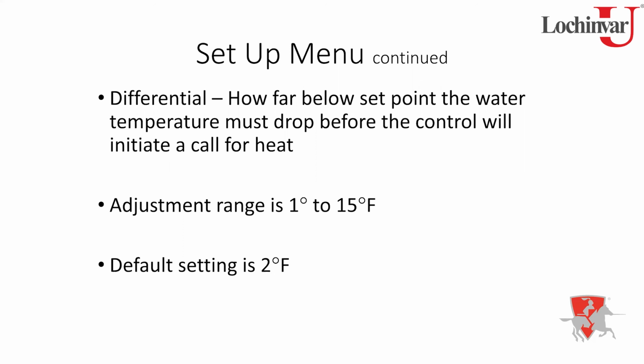Again, you don't want to go too wild with it, because especially in a pool setting, if you put like 10 degrees there, and let's say my pool set point was 80, that means it's got to drop to 70 before it kicks off. That's a big swing too. Yeah, that's a pretty big swing. People are going to notice, especially in a pool. So again, keep that range kind of tight. 2 to 3 degrees is probably where you're going to ride with that one. Now, I don't see too many people adjusting that particular parameter.